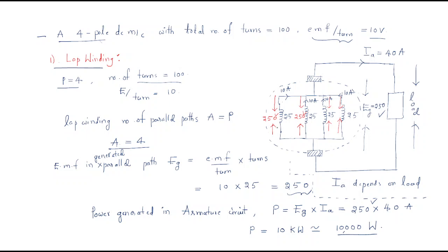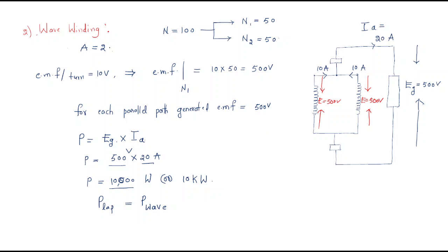In lap winding there are four parallel paths, so the 100 turns are divided into four parts, giving 25 turns each. In wave winding there are only two parallel paths, so turns are divided into two parts of 50 turns each, generating 500 volts EMF. For 10 kilowatts load, each parallel path carries 10 amps and the total current is 20 amps.